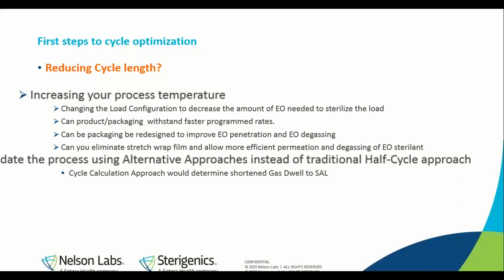Okay, what this does is it will help conduct the same amount of phases in your sterilization process, but just look at, see if we can shave off minutes in each of the phases. Cumulatively, you would be able to reduce cycle length. Can the packaging be redesigned to improve EO penetration and EO degassing?